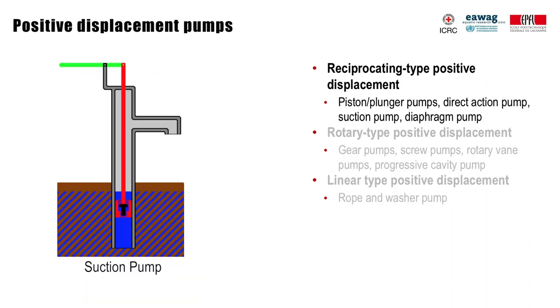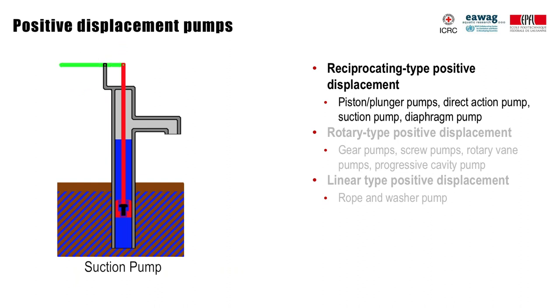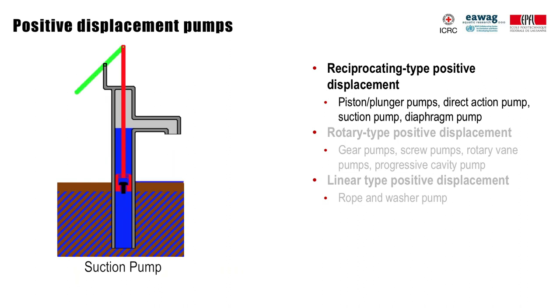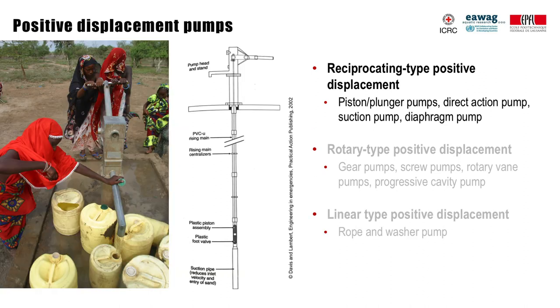Reciprocating type positive displacement pumps are commonly used in a number of applications. Many community hand pumps for dug wells and boreholes are reciprocating piston or plunger pumps. When water is available less than 7 meters below ground, suction pumps are often of interest as they can be easily accessed at ground level to perform maintenance. For deeper wells and boreholes, direct action hand pumps or high lift hand pumps can be used.